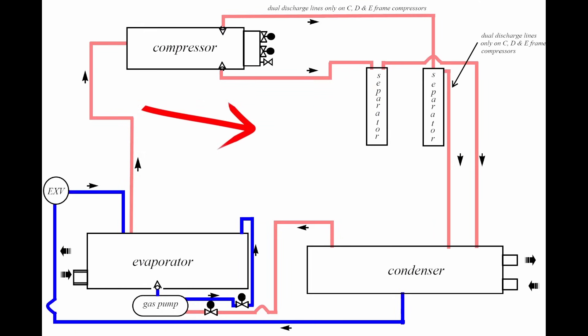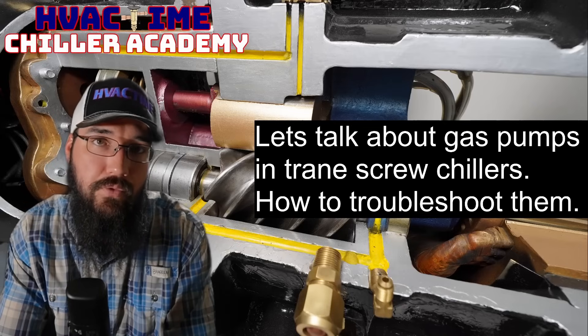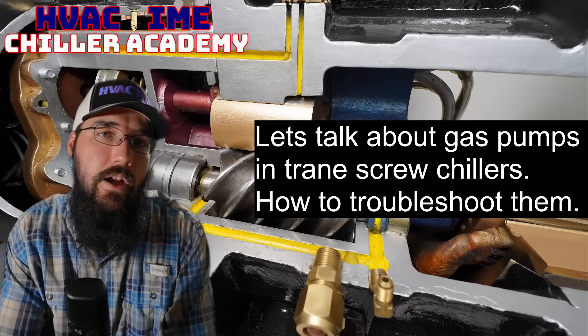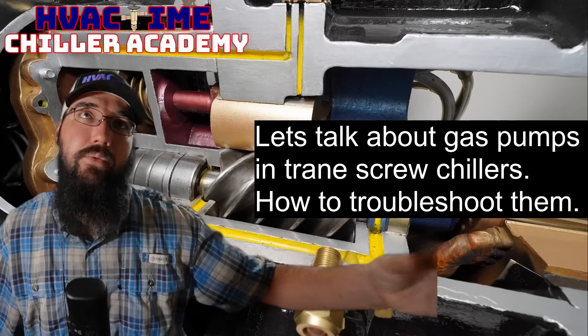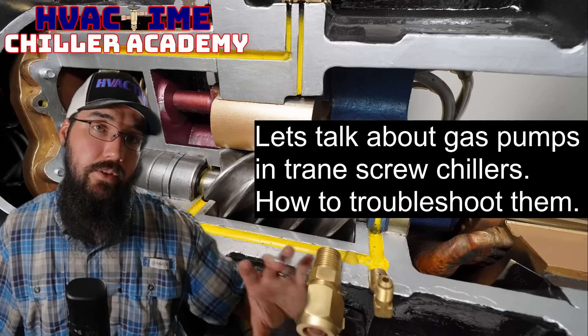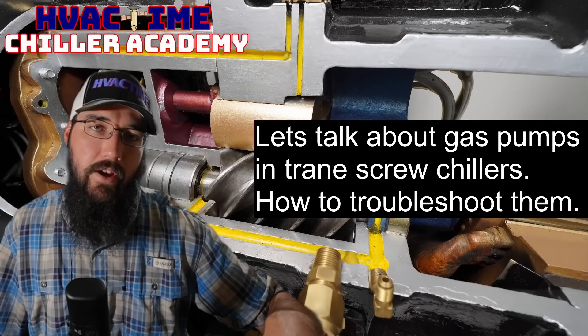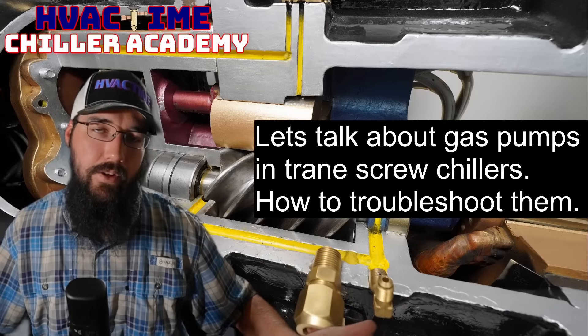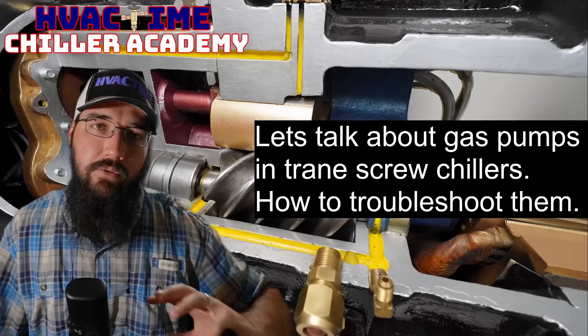In terms of troubleshooting, the typical symptom is a low suction pressure issue or high approach values — meaning you're not properly transferring heat even though your liquid level sensor feedback shows you're at the correct set point. Your evaporator pressure will be lower than expected and approach will run higher than it should. This is evidence that oil is laying in the evaporator and you're not transferring heat properly.